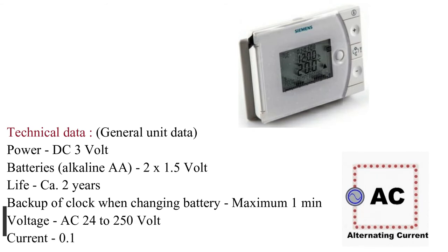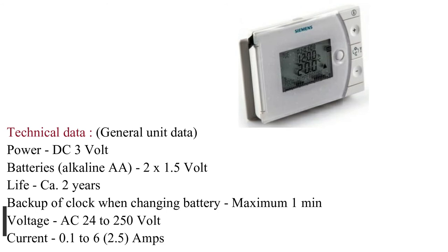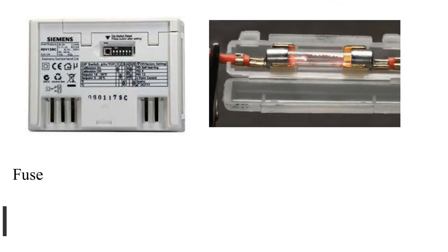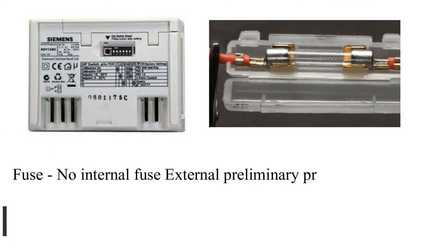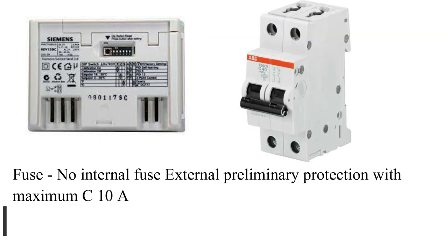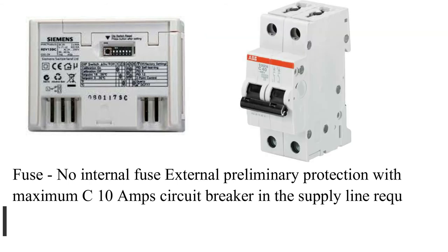Switching capacity of relay: voltage AC 24 to 250 volt, current 0.1 to 2.5 amps. Fuse: no internal fuse — external preliminary protection with maximum C10 amps circuit breaker in the supply line required under all circumstances.